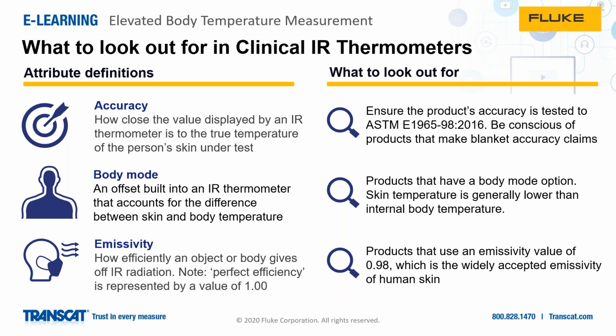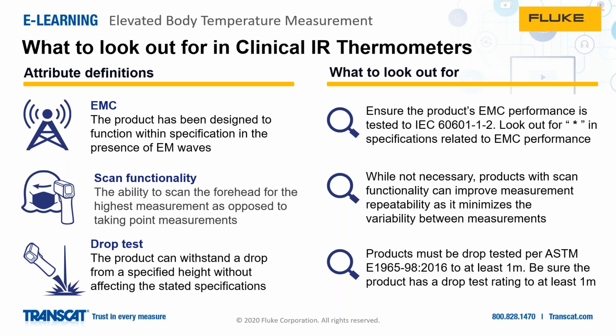Emissivity, which is essentially a measure of how efficiently an object gives off IR radiation. You want to look out for products that use an emissivity value of 0.98, as this is the widely accepted emissivity value of human skin. Looking at the EMC performance, you should ensure that the product's EMC is tested to the IEC 60601-1-2 standard, also called out in the FDA's enforcement policy. You might also look out for asterisks within the specifications related to the EMC performance.